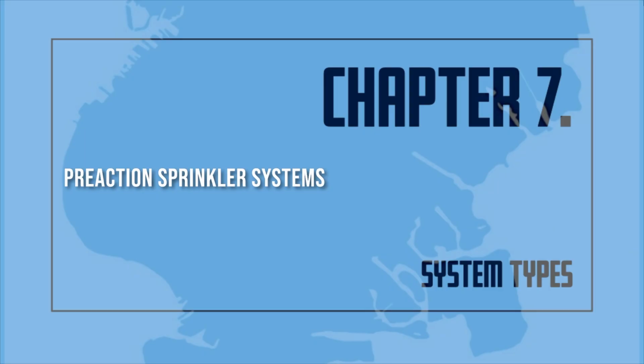Under normal conditions, there is no water in the piping. The air in the piping may or may not be under pressure. A pre-action valve prevents the water from entering the system. The valve is automatically opened when a fire detection system discovers that there is a fire or smoke condition. The pre-action valve is tripped by the fire detection system before any of the sprinkler heads open.